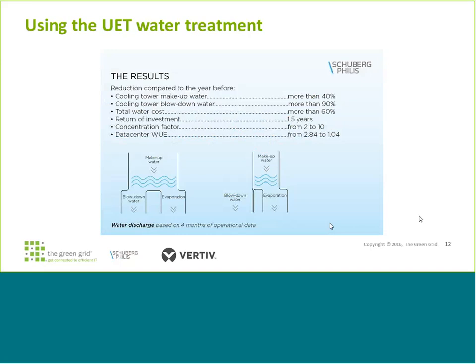So reduction 40% we already talked about. Blow down water less, as you dropped by 90%. Your total water cost has gone down then by more than 60%. Interesting, the payback, so return on investment, approximately 1.3 years, but I think that was a more conservative number. And if you could talk then to the concentration factor and how you worked out the WUE.